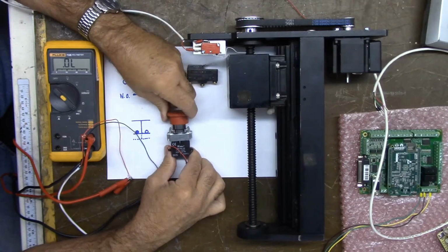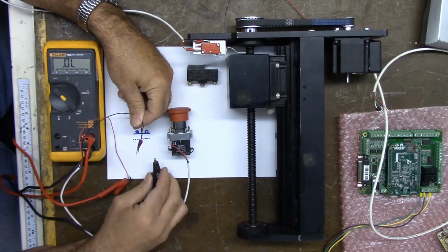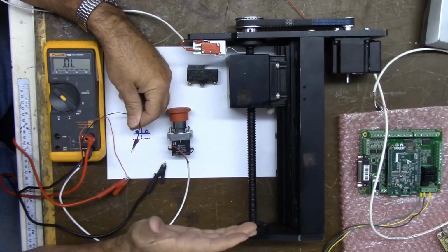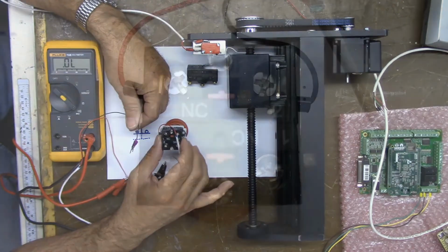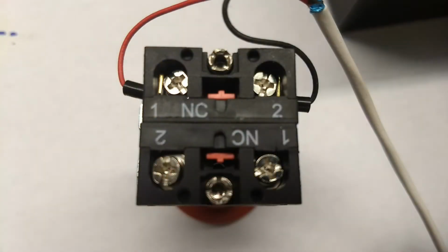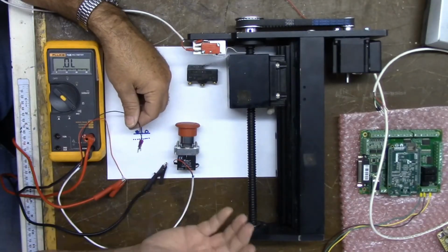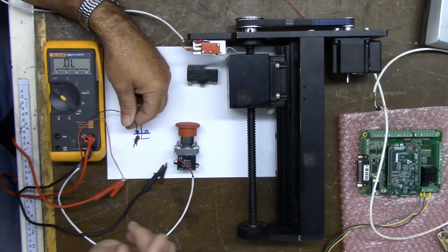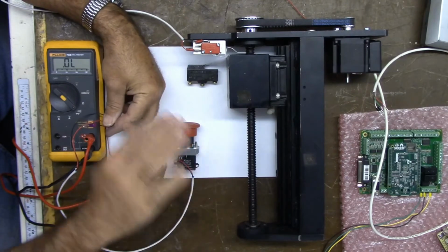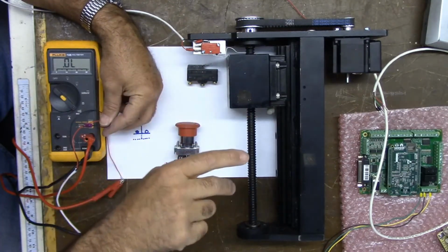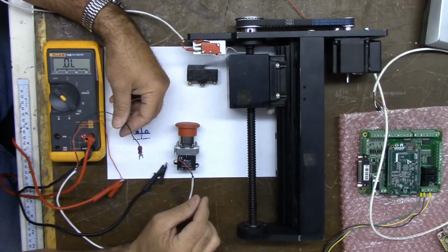The reason why this is important is if a wire breaks, the circuit opens and the machine will stop. The control will see an open circuit and the machine will stop. That's why you want to use normally closed. If you used a normally open circuit, the control is happy not seeing a signal, but as soon as it sees a signal, it will stop. Well, if you break a wire, it will never have the ability to see a signal. You're going to hit that button, you're closing a circuit, and the wire's broken. It will never see a signal, and you could have a big crash.